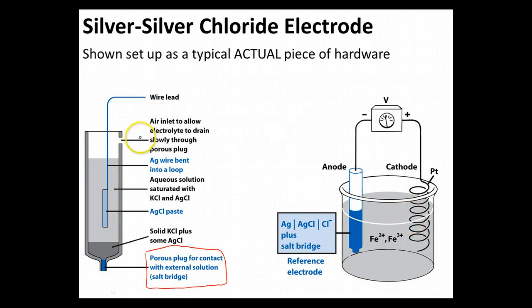So you can see here we're going to have an air inlet that's open. The reason we always have to make sure we open the air inlet on any of the probes that we use is we need to allow a tiny amount of the fluid to actually pour through the salt bridge if needed.